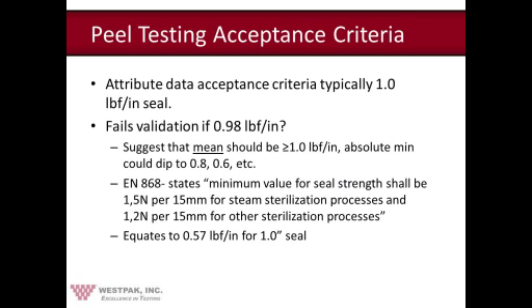There's a little known document out there called EN 868-5 that states that the minimum value for seals that have been steam sterilized is 1.5 newtons per 15 millimeter seal. Now, this translates to a minimum seal strength of 0.57 pounds for a 1-inch seal, which is typically what we use here in the Americas.